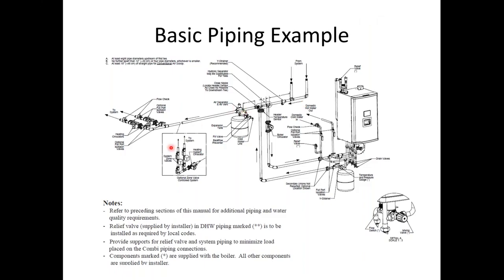Showing piping the combi, in some cases you will need a thermal expansion tank for the domestic hot water side. I'm not sure if your jurisdiction is one of the areas that are requiring backflow prevention or dual check valves on the meters, in essence making the potable water system a closed system. If that's the case, you would need to put in a thermal expansion tank so the relief valve does not start doing its job.